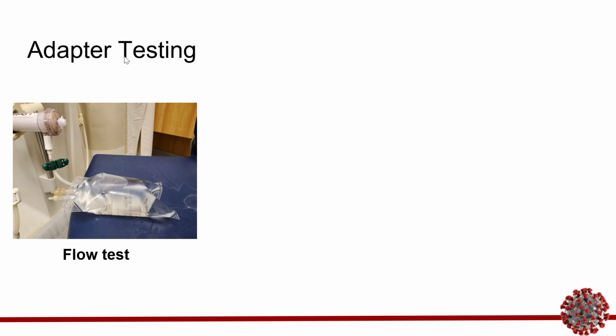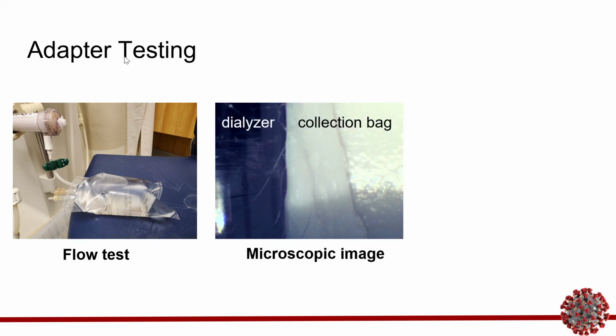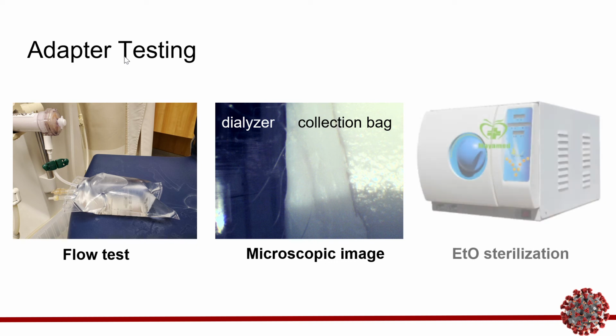The next step was to test the adapter. We started by sending the highest possible flow rate of dialysate through the system to ensure that the adapter could withstand this pressure without the dialysate leaking out. Next, we wanted to ensure that the dialysate makes no contact with the adapter, since the adapter is 3D printed and could possibly leach polycarbonate into the dialysate. To test this, we took microscopic images of the interface between the dialyzer and the collection bag. We saw no air gap between this interface, showing that the dialysate makes no contact with the adapter. Finally, we performed 3 cycles of ETO sterilization and measured the critical dimensions of the adapter before and after each cycle to ensure that it did not deform.